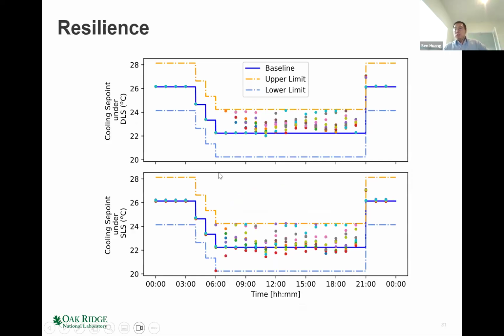And then we can also see that from the room temperature. Again, we plot the room temperature set point, which is the output from the power dispatch signal. When we do the conventional deterministic optimization, you can see the temperature set point is, for most cases, above the baseline. That means for most cases, we are actually curtailing the usage of power in the building. So basically, we make people suffer when we're trying to provide demand response.